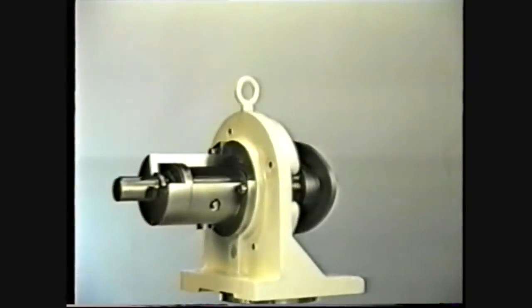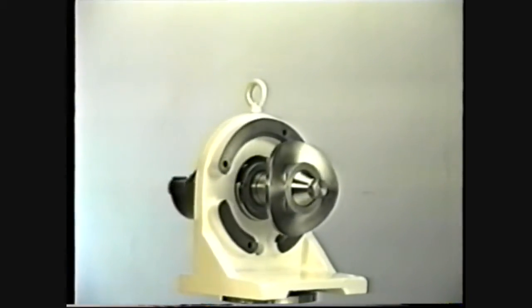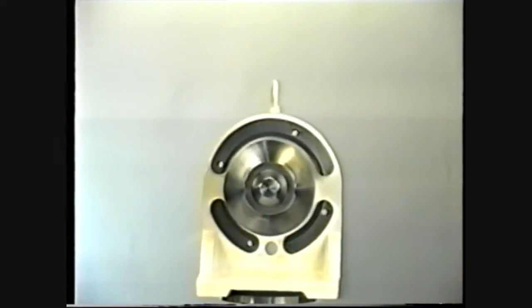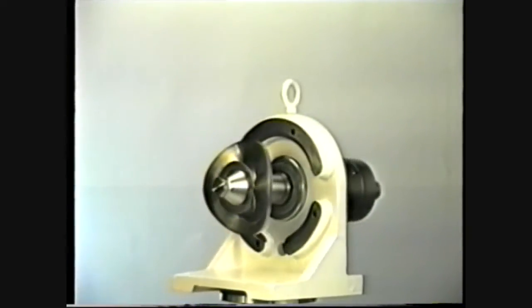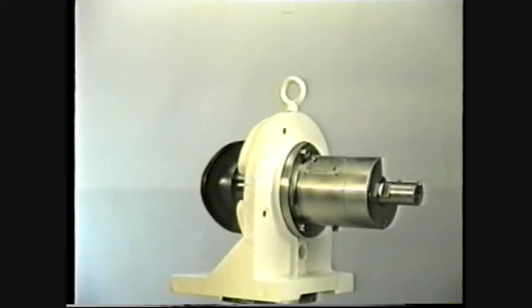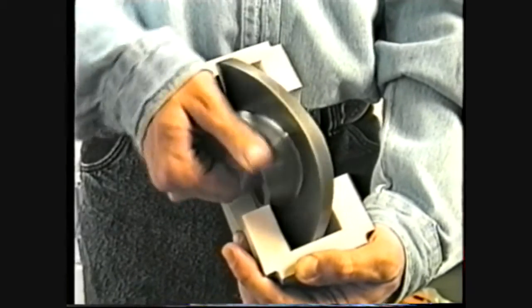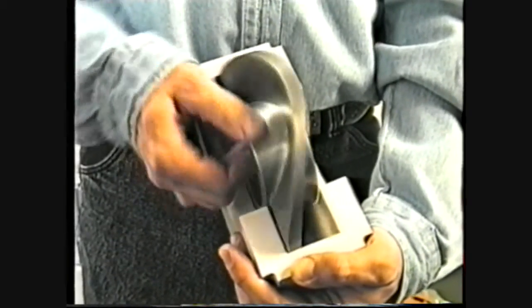Let's take a closer look at this innovative pump. Sine Pump uses a single shaft to drive a single sinusoidal shaped rotor. The sine wave of the rotor creates four cavities of equal volume which capture the product between two symmetrical liners and move it through the pump, producing a smooth laminar discharge stream.